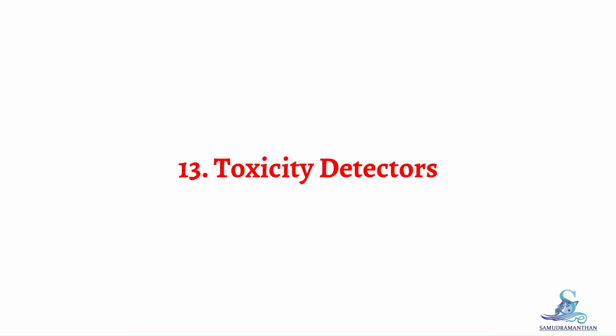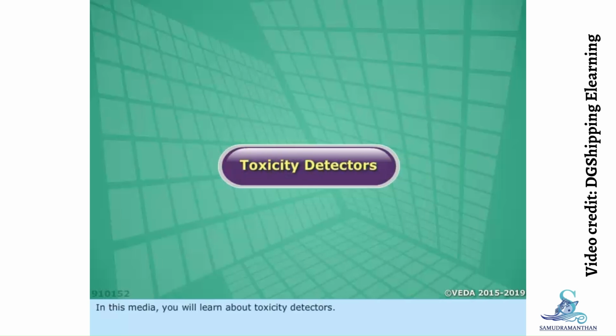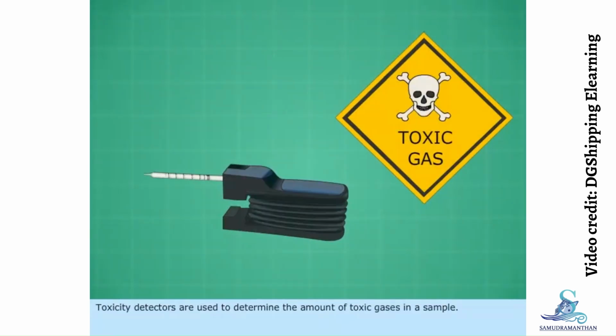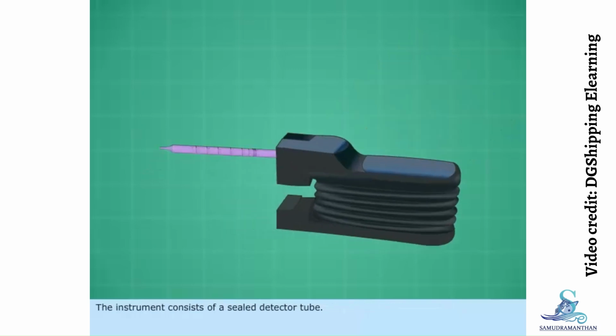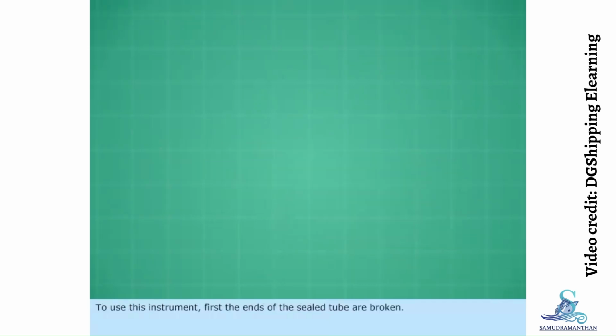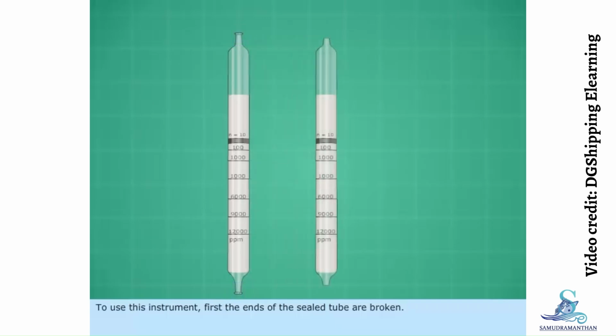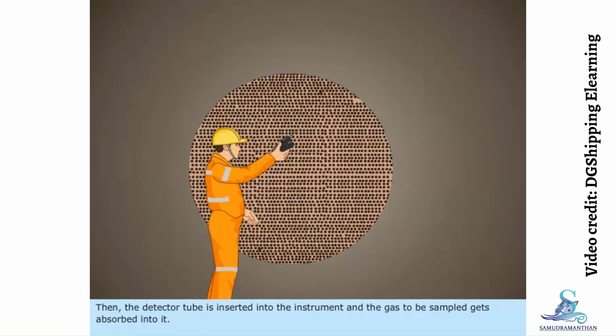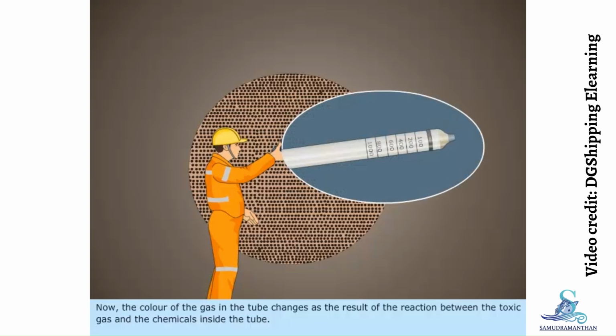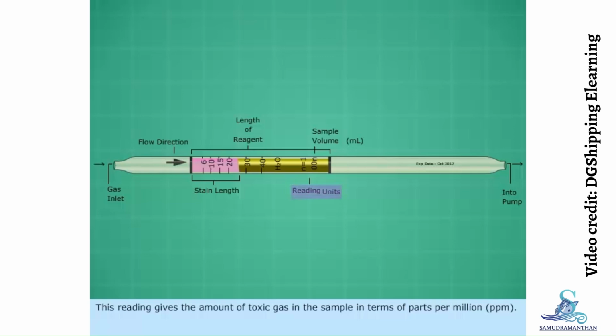Topic 13: Toxicity Detectors. In this media, you will learn about toxicity detectors. Toxicity detectors are used to determine the amount of toxic gases in a sample. The instrument consists of a sealed detector tube. To use this instrument, first the ends of the sealed tube are broken. Then, the detector tube is inserted into the instrument and the gas to be sampled gets absorbed into it. Now, the color of the gas in the tube changes as the result of the reaction between the toxic gas and the chemicals inside the tube. The color stain rises against the scale reading marked in the tube. This reading gives the amount of toxic gas in the sample in terms of parts per million, ppm.